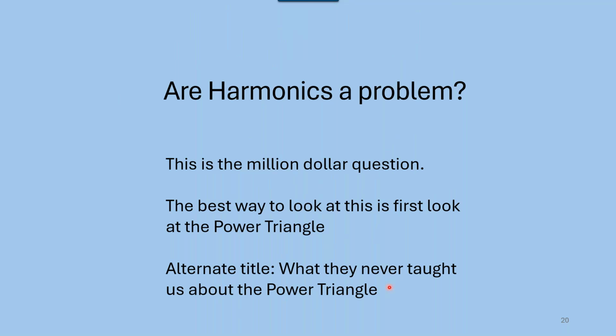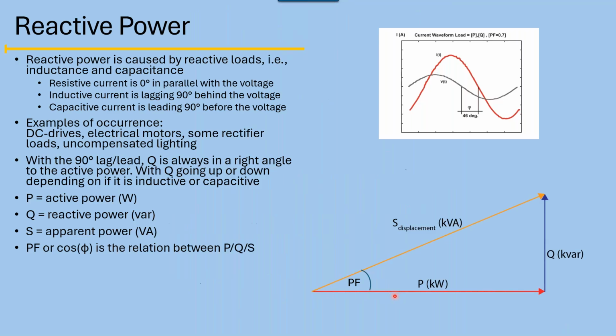The electrical engineers on the call will definitely get a good laugh out of this one, because they never taught us about this. So let's talk about the power triangle. We know that kW does real work. kVAR is either inductance or capacitance. When you add them together, we have our displacement kVA. Very simple. The beauty about reactance is it's always 90 degrees to the kW. If it's capacitance, it'll be one direction, and if it's an inductor, it'll be the other direction.